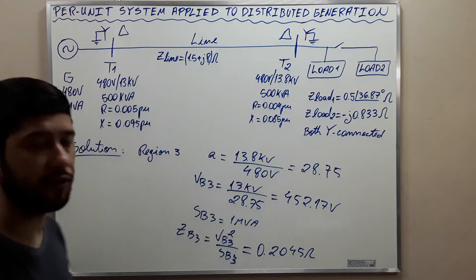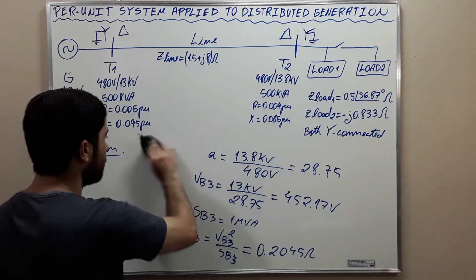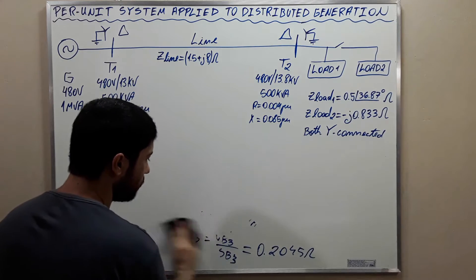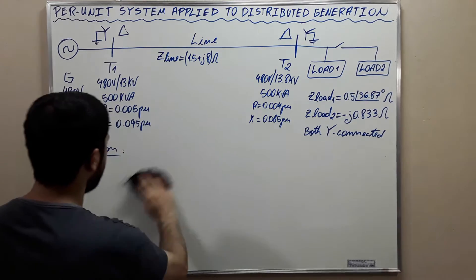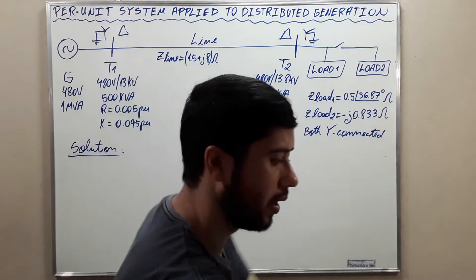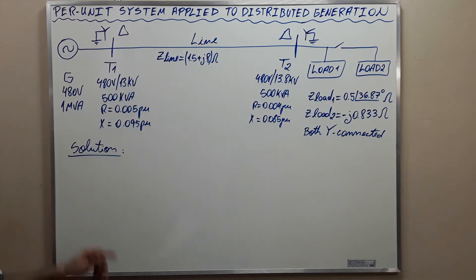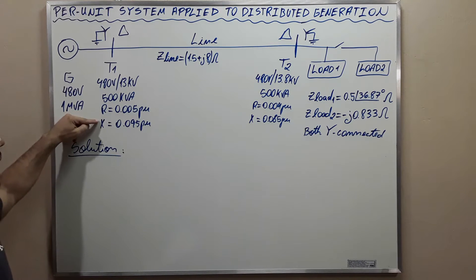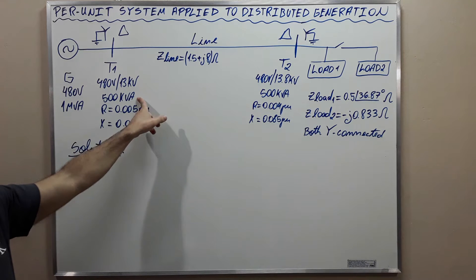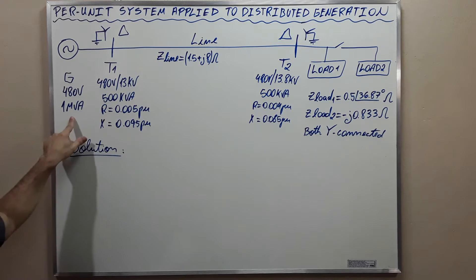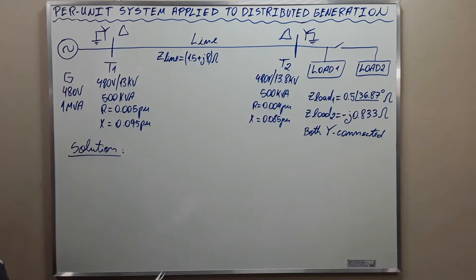Now let's do the adjustment. We need to adjust the transformer impedance values because we are using different values for the base apparent power — instead of using 500 KVA, we are using 1 MVA. Therefore, we will need to carry out these adjustments using the conversion expression.